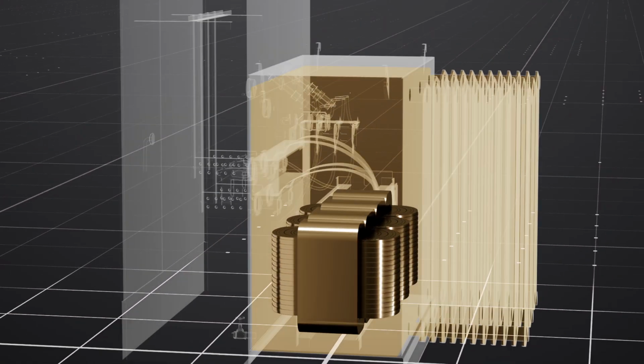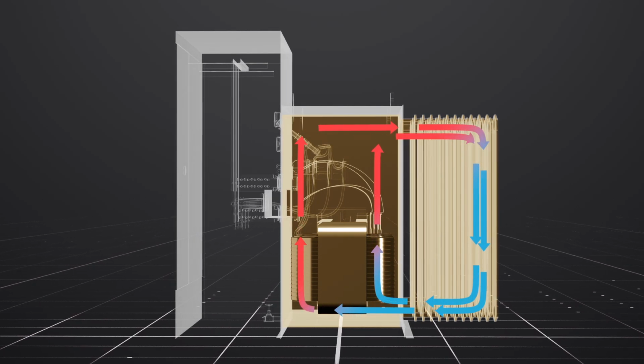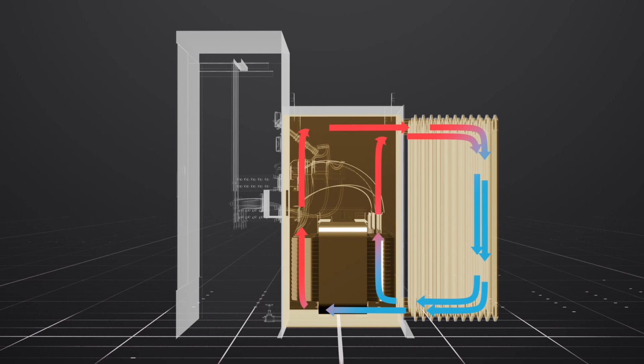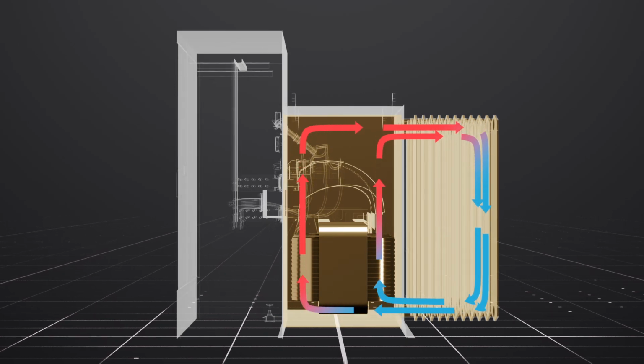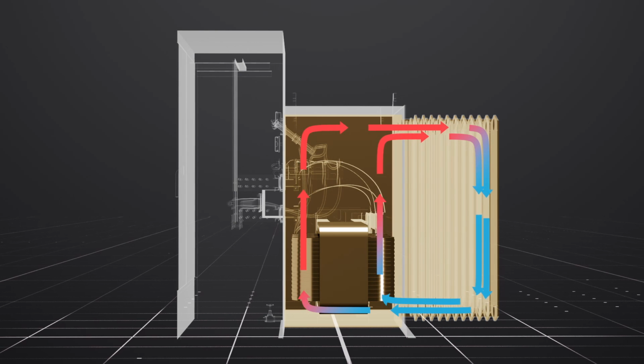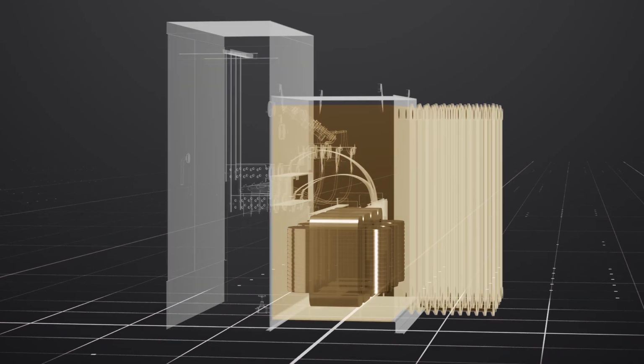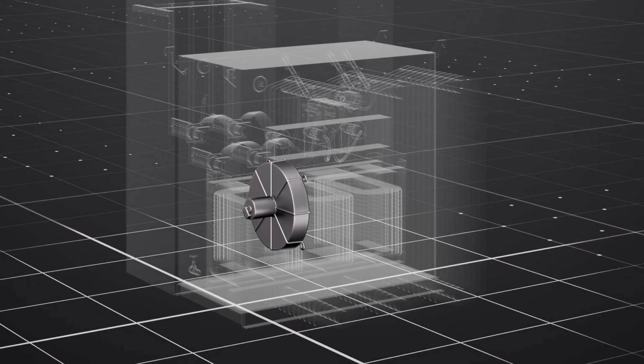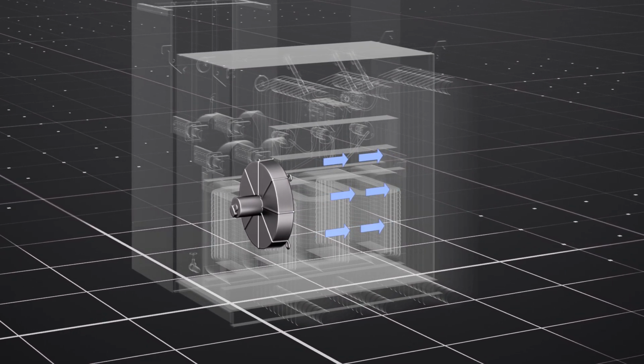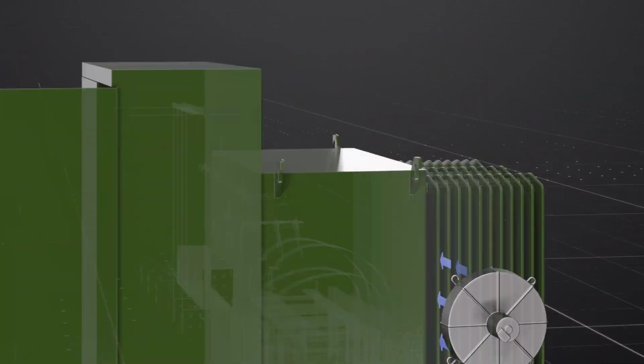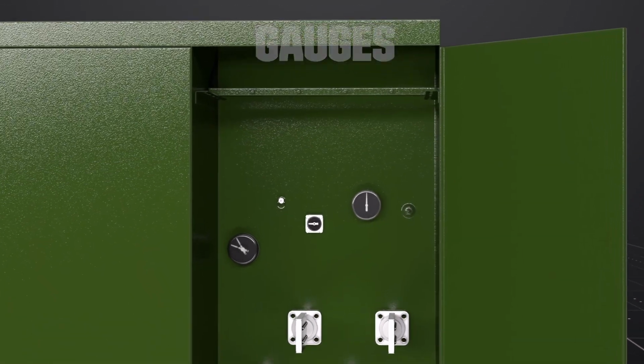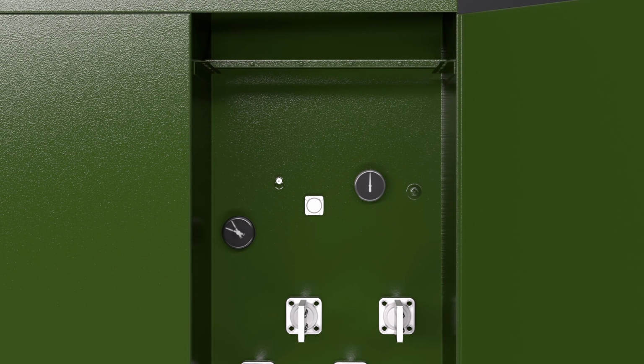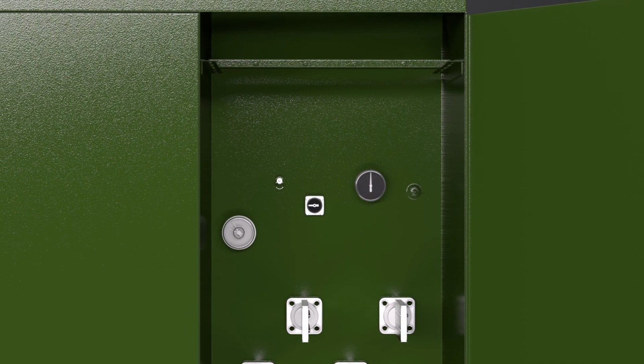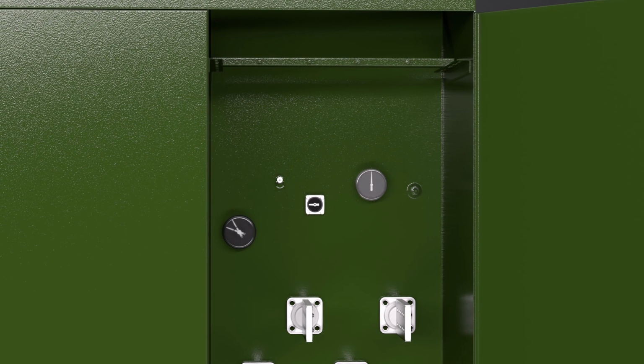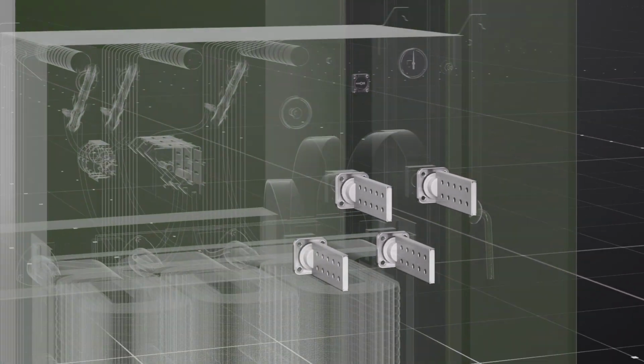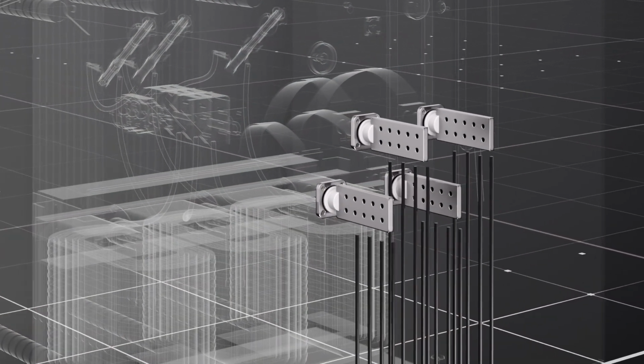As the fluid rises in temperature, it rises to the top of the tank. It enters the radiators, where the ambient temperature cools it off. As the fluid cools, it drops to the bottom of the radiators and re-enters the tank. This process is called natural convection. Some transformers come with fans which blow cool air through the radiator fins, speeding up the cooling process. Gauges are used to monitor operating conditions. The liquid level gauge monitors the level of the fluid inside the tank. The thermometer measures the temperature of the fluid, and the pressure vacuum gauge monitors the amount of pressure inside the tank. The low voltage bushings connect the load to the transformer.